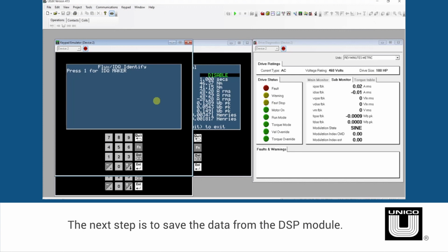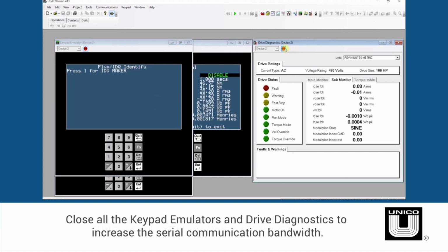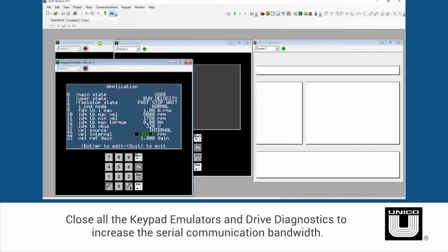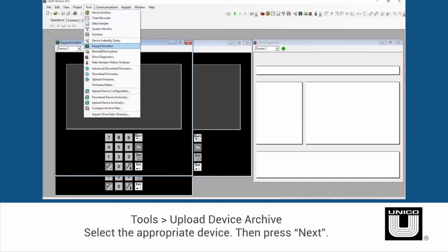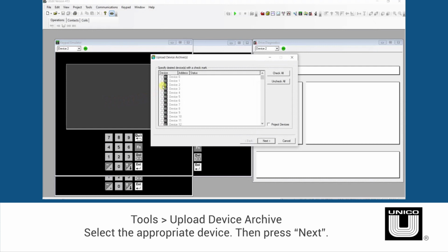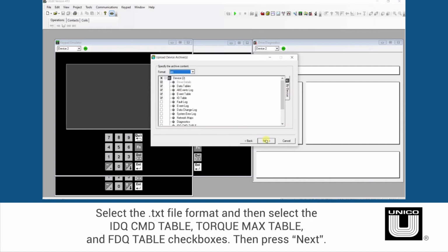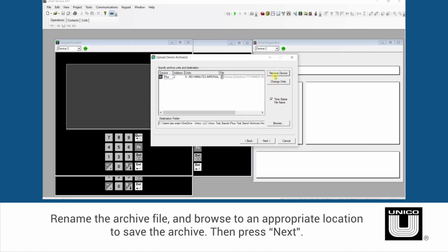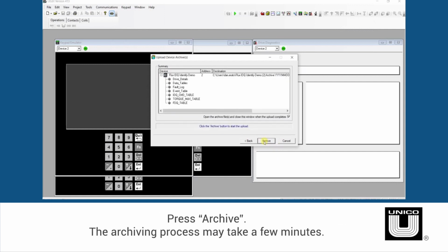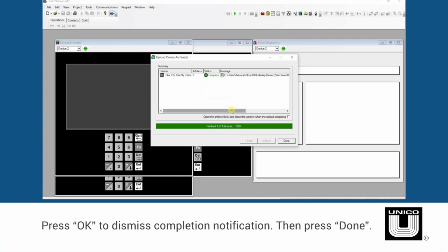The next step is to save the data from the DSP module. First, close all the keypad emulators and the drive diagnostic window to increase the serial communication bandwidth. Then go to Tools, Upload Device Archive, and select the appropriate device. Select the text file format and then select the IDQ command table, torque max table, and FDQ table checkboxes. Rename the archive file and browse to an appropriate location to save the archive. Then select Archive. Once complete, select Done.